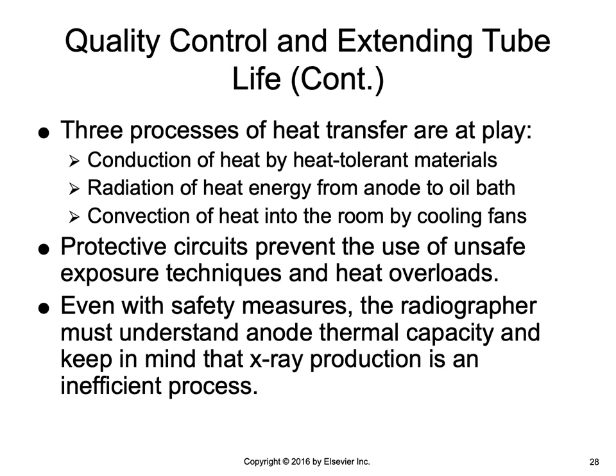There are three processes of heat transfer at play: the conduction of heat by heat-tolerant materials, the radiation of heat energy from the anode to the oil bath, and the convection of heat into the room by the cooling fans. Modern x-ray machines have protective circuits built in that prevent the use of unsafe exposure techniques and prevent heat overloads of the x-ray tube. However, even with all these safety measures, the radiographer must understand anode thermal capacity and keep in mind that x-ray production is a very inefficient process — almost 99% of the energy is converted to heat, and only 1% is converted to x-ray.